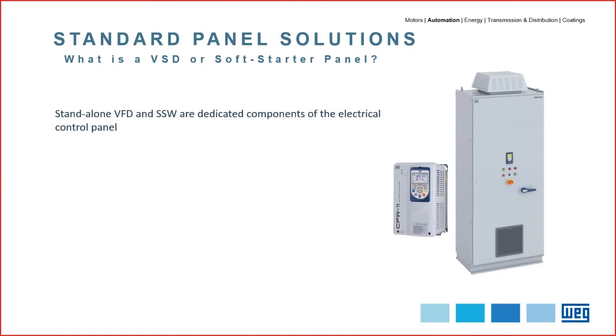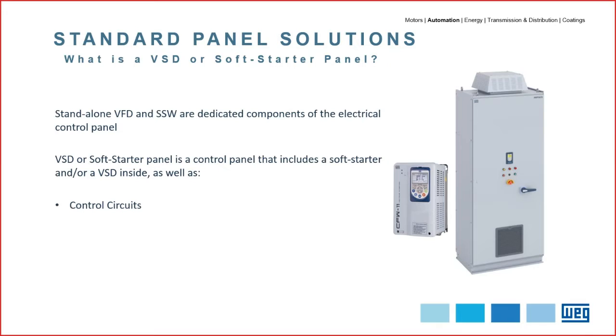Before we discuss what a VSD or a soft starter panel is, we must consider that standalone VSDs and soft starters are dedicated components of the electrical control panel. So we can define a VSD or a soft starter panel as a control panel that includes a soft starter and/or a VSD inside, as well as the control circuits, protection components, additional electrical components, and counts with a protection enclosure. These additional electrical components of the panel are all chosen according to the VSD and soft starters' different functions and applications. Great, but when should we specify a VSD or a soft starter panel instead of a standalone VSD and soft starter?